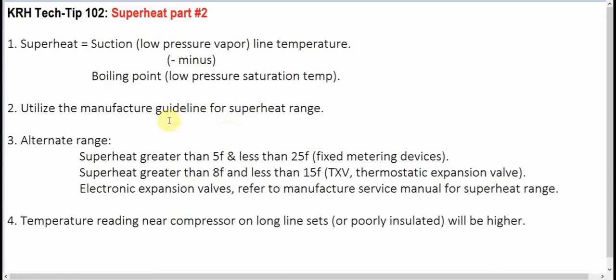So the alternate range that I have found to be is the superheat should be greater than 5 degrees and less than 25 degrees in fixed metering device systems. Now, a fixed metering device system is a system that uses a piston actuator, a capillary tube, or uses the restrictor in the distributor. This type of metering device does not regulate.